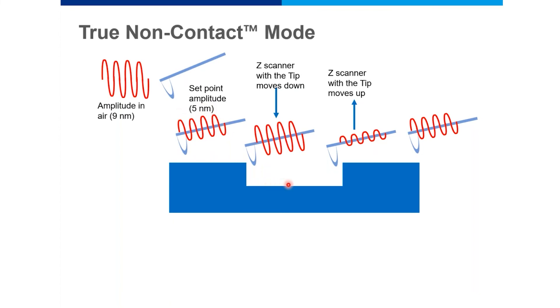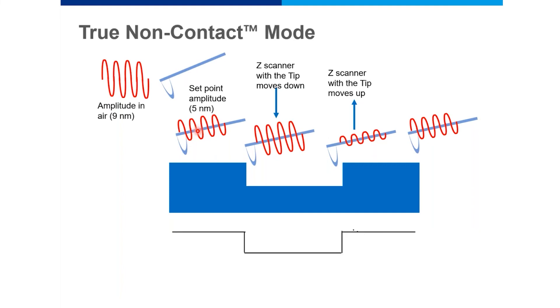Similarly, when the tip scans a hilly area, the distance between the cantilever and the sample becomes very small, the interaction forces increase, and the amplitude decreases significantly. The feedback mechanism then tells the Z-scanner to move slightly up to maintain the five-nanometer set point. Depending on the features of the sample surface, the Z-scanner moves up and down, always adjusting the tip to maintain the set-point amplitude of five nanometers — and this is how you generate the image of the sample surface.